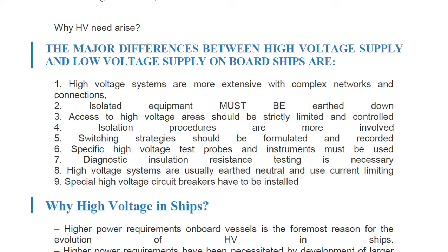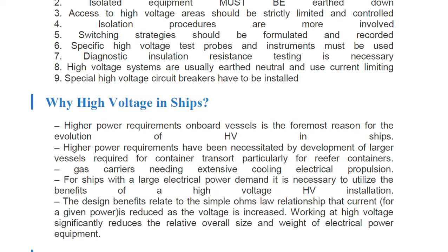The major differences between high voltage and low voltage supply on board ships are: HV systems are more extensive with complex networks and connections; isolated equipment must be earthed down; access to high voltage areas should be strictly limited and controlled; isolation procedures are more involved; switching strategies should be formulated and recorded; specific high voltage test probes and instruments must be used; diagnostic insulation resistance testing is necessary; high voltage systems are usually earth neutral and use current limiting; and special high voltage circuit breakers have to be installed.